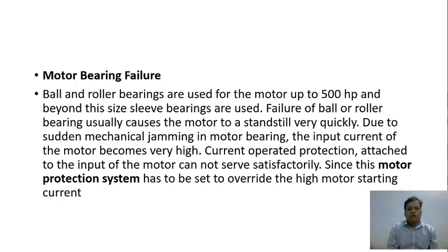The failure of a ball or roller bearing usually causes the motor to stand still very quickly. Due to sudden mechanical jamming in the motor bearing, the input current of the motor becomes very high. Now the current operated protection attached to the input of the motor cannot serve satisfactorily, since this protection has to be set to override the high motor starting current. So we should avoid this motor bearing failure. It is a very hazardous thing.